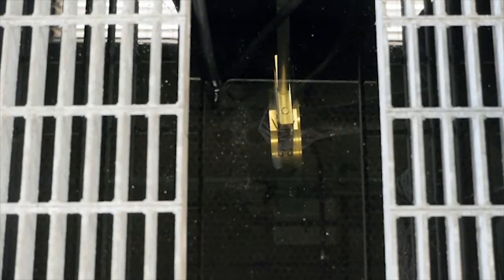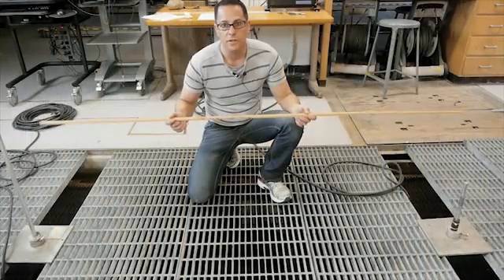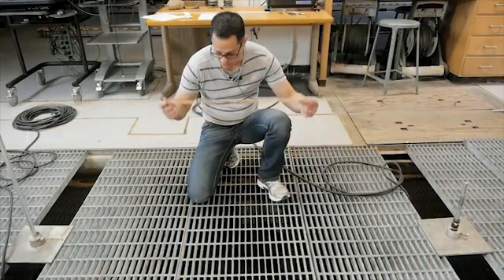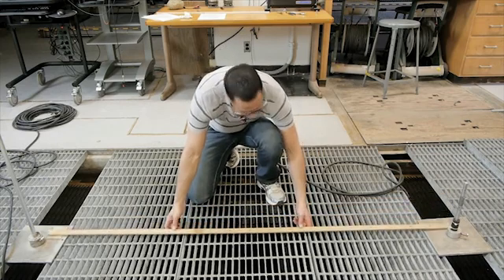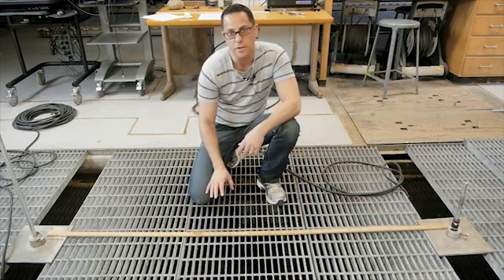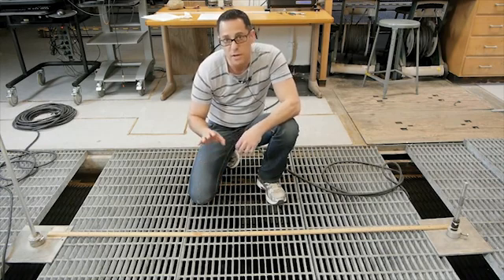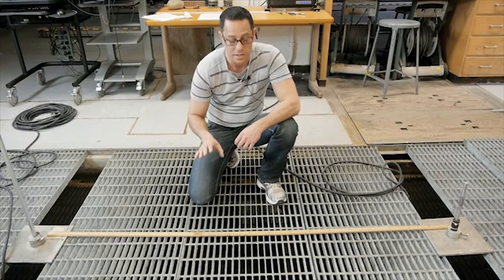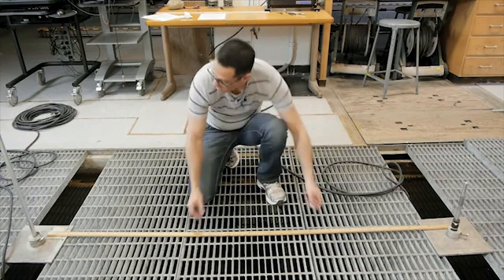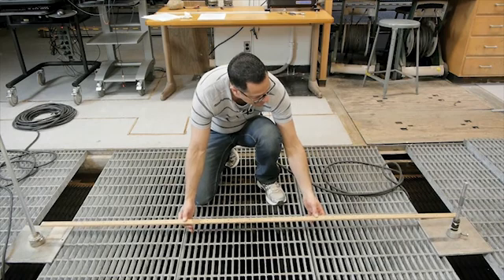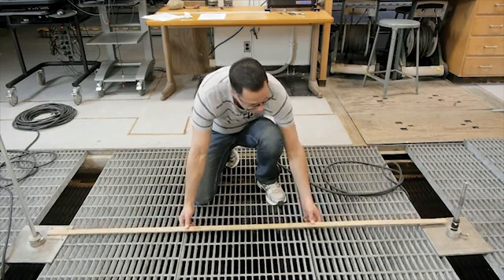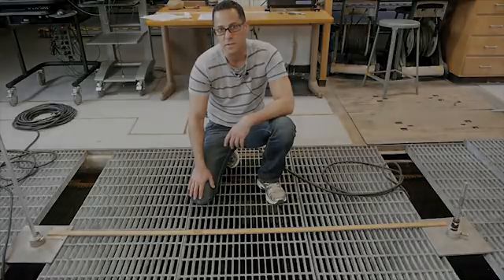You want to make sure that the transducer is facing your other transducer. You want them to be parallel. You don't want it to be twisted at an angle like this. Make sure that you measure the distance between the two transducers with a 2-meter stick. It's not important that they be 2 meters apart exactly. What's important is that you know the exact distance and that you keep the distance exactly the same for each measurement. To keep things simple, I measure from the center to the center of each of these poles rather than trying to get the face of the transducers.